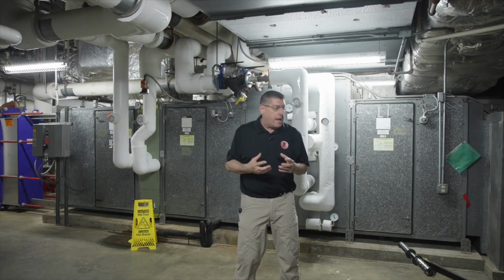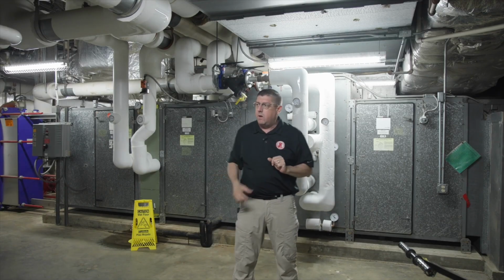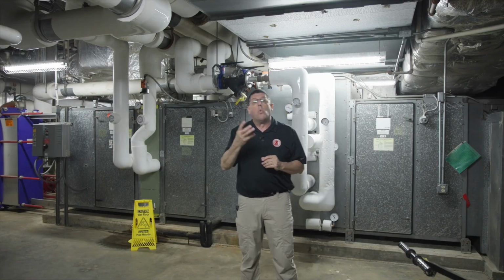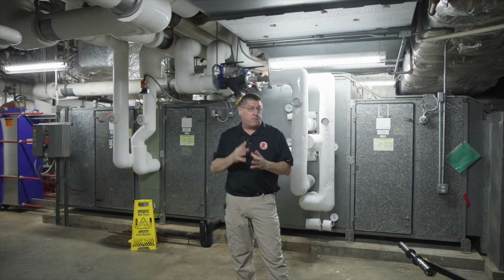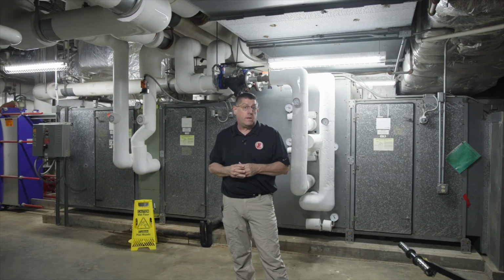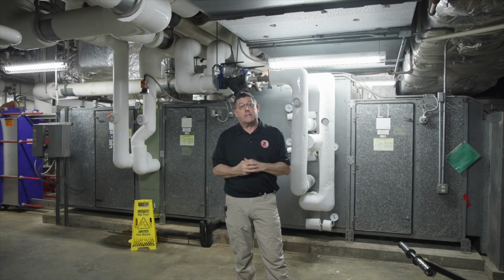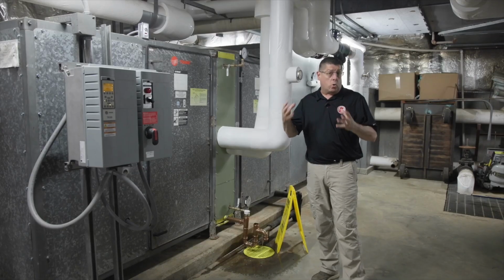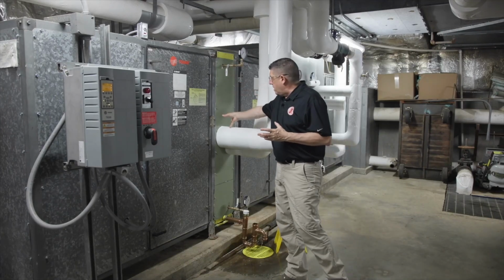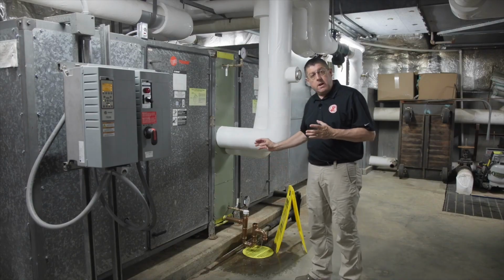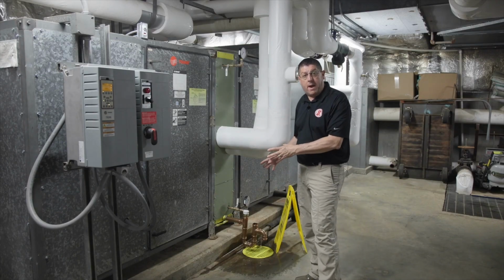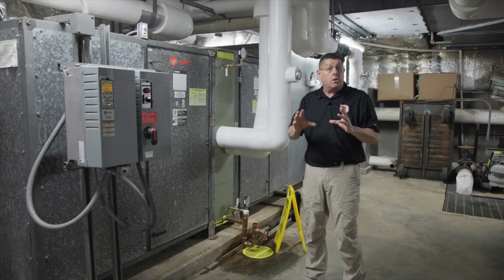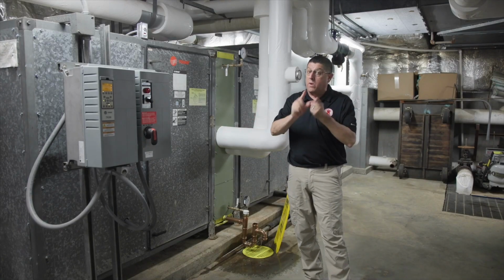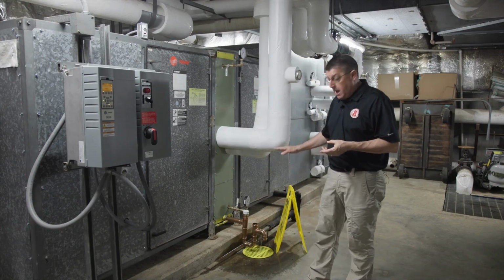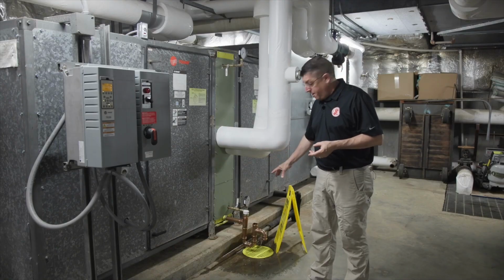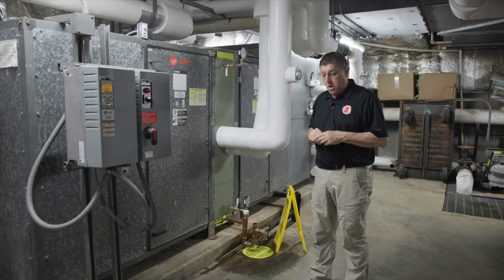Now, the next thing I want to look at, if I've got the heating coils over here and the cooling coils on this side, what is evacuating off the bottom of any cooling coil? Condensation. So let's go look at that next. On our cooling side, and as this is my cooling coil, I do have a condensation drip pan. And that is always, just like any other HVAC equipment we inspect, has to have a drip pan with a trap.